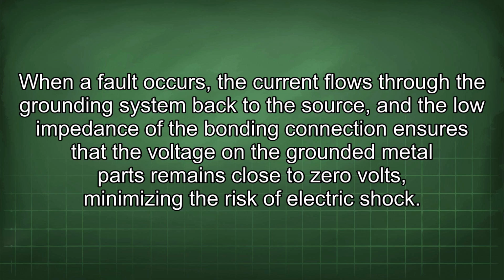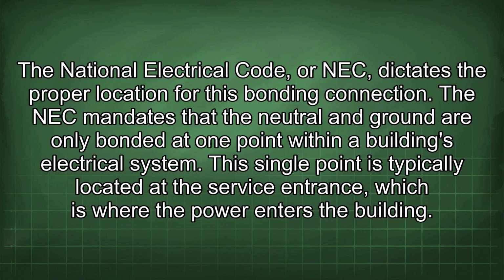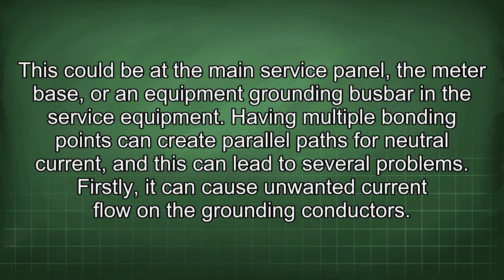of electric shock. The National Electrical Code, or NEC, dictates the proper location for this bonding connection. The NEC mandates that the neutral and ground are only bonded at one point within a building's electrical system. This single point is typically located at the service entrance, which is where the power enters the building. This could be at the main service panel, the meter base, or an equipment grounding busbar in the service equipment.